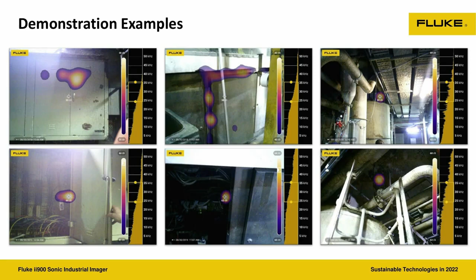The ii900 can find leaks from up to 50 meters away. As Sam mentioned, our ii910 variant does all of this plus picks up partial discharge on high voltage networks, identifying and locating it from up to 110 meters away. The unit itself isn't intrinsically safe, but being able to identify and capture these air leaks or partial discharge hopefully lets you stay outside the zone 1 area, though you may still need a hot works permit.